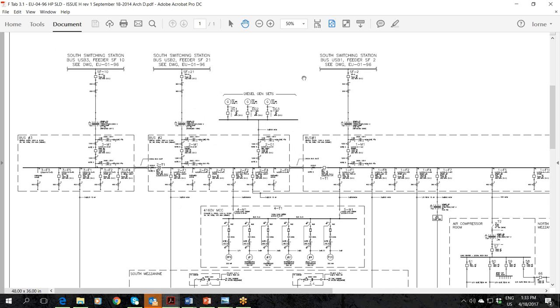The black start's very critical for us because if the heating plant ever loses power, we'd need these to black start the heating plant, which then in turn would help us to get one of our steam turbine generators going, if not both, which would then power the campus itself. They don't have enough capacity on their own to be self-sufficient as a campus.